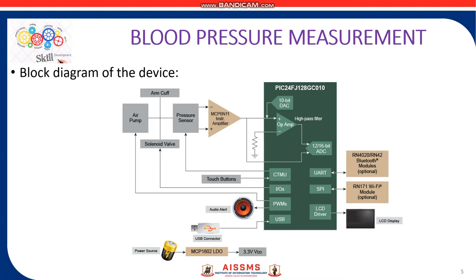When the cuff is fully inflated to this pressure, no blood flow occurs through the artery. This pressure is then gradually released using a digitally controlled solenoid valve until the moment that blood begins to flow through the artery. As the cuff is deflated below the systolic pressure, the reducing pressure exerted on the artery allows blood to flow through it and sets up a detectable vibration in the arterial wall. The blood pressure measured by the pressure sensor at this point determines the systolic pressure.